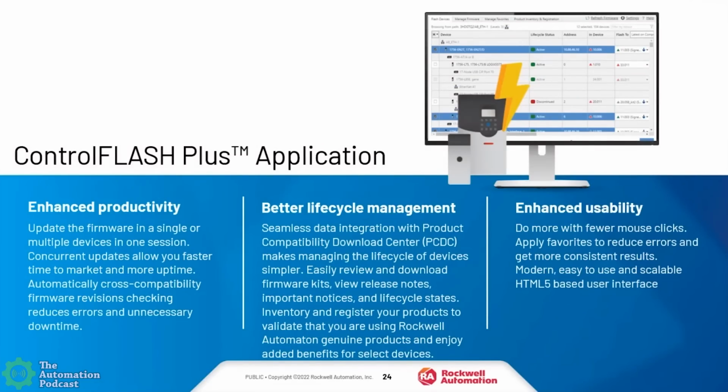This is a very powerful tool, allowing multiple devices to get flashed at once, and it is a definite value add. From the software, you can get the latest firmware and get more done in less time. We talked about the download workflow with the Logix SDK, and this is something very similar, in my opinion, when it comes to flashing. There are steps you have to take in order to flash a controller, and these can take some time. So doing them individually, especially if you have a lot of controllers, is less than ideal. With Control Flash Plus, up to 20 devices can be flashed at the same time.